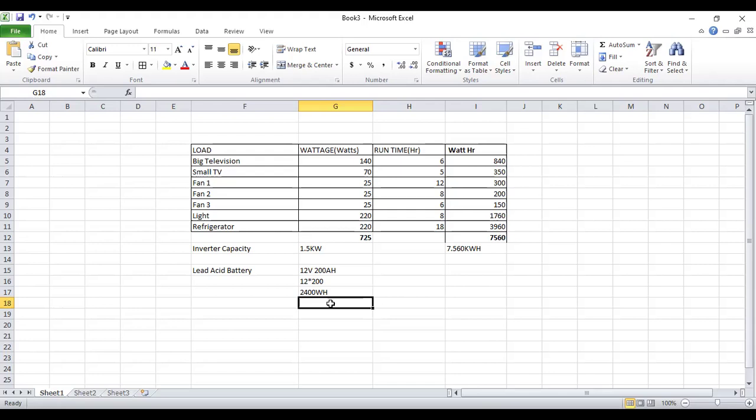If not, the lead acid battery doesn't have protection. It doesn't have a battery monitoring system. So if you continue to drain it below the operating voltage range, then you will definitely have issues with the battery lifespan. It will definitely affect the battery lifespan. You understand? So each battery has its own depth of discharge. If this battery is rated to have 60% depth of discharge, you need to confirm all these things when buying these types of battery.